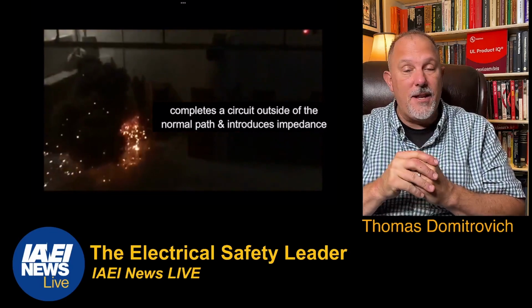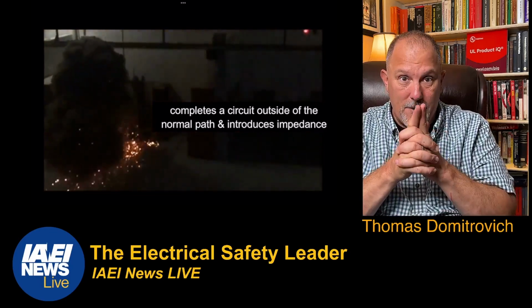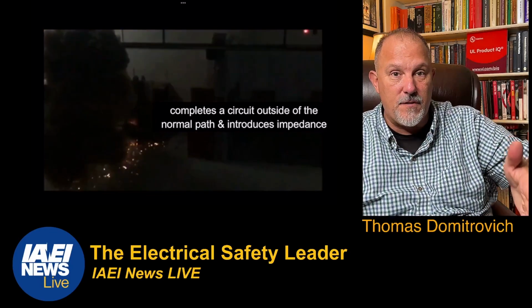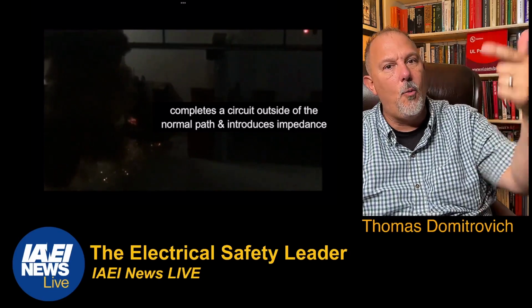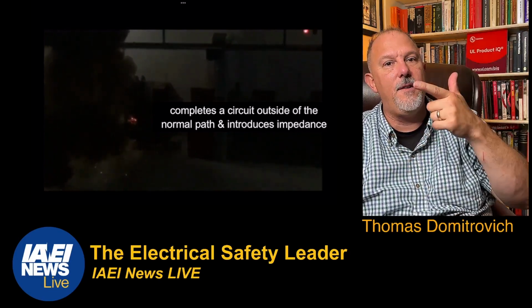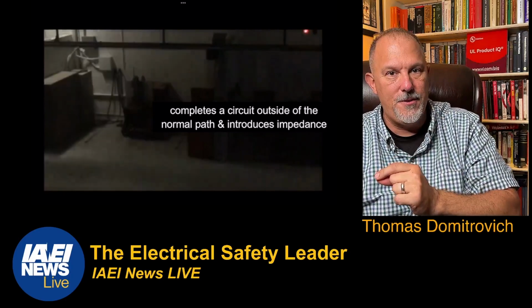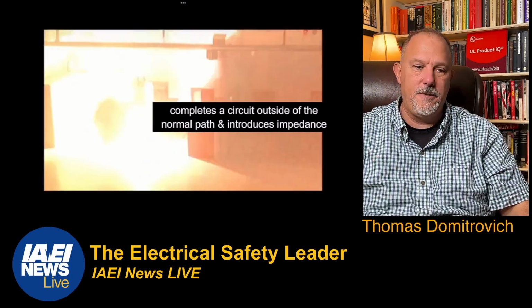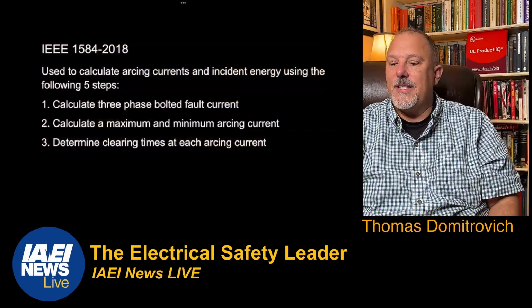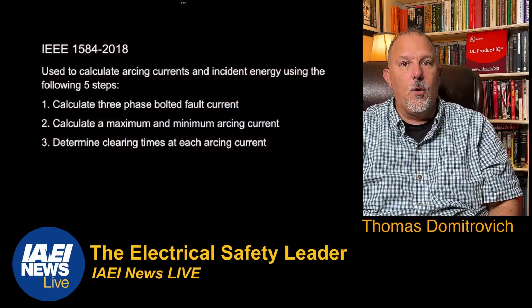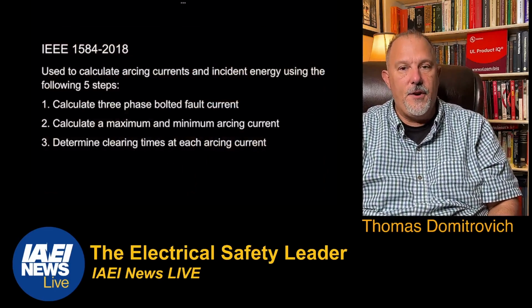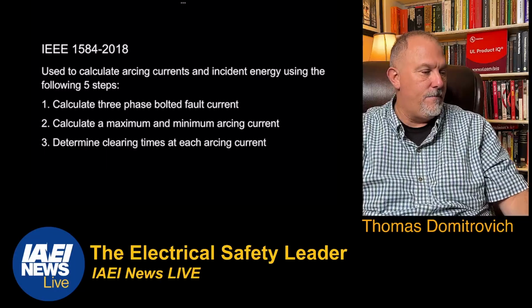Now, the challenge that we have is, how do I calculate this? Remember, I know how to calculate a three-phase bolted fault current value. The impedance is 0, but what is the impedance of that plasma cloud? That's the challenge. That's what IEEE 1584 does for us. It gives us those equations. Now, I'll tell you how we came up with that.